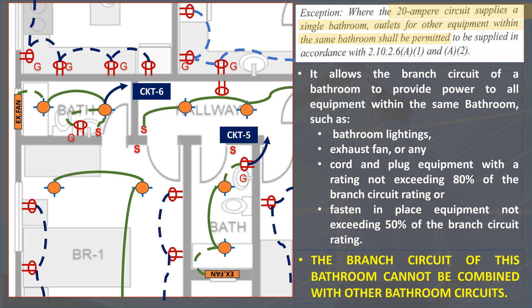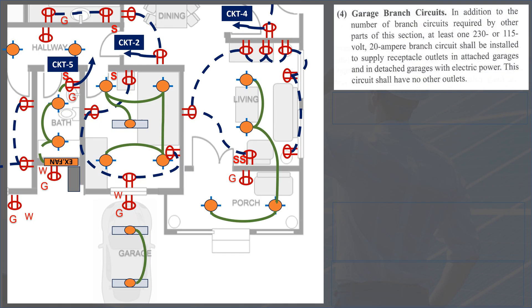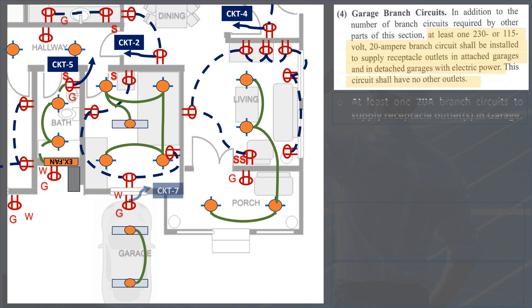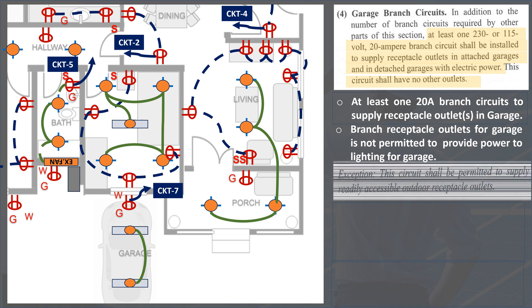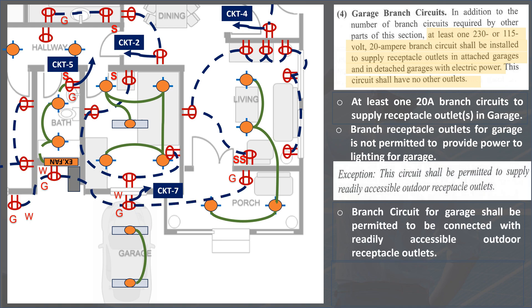The branch circuit of a bathroom cannot be combined with other bathroom circuits. Garage branch circuits: paragraph 4 of Section 2.10.1.11C states that in addition to the number of branch circuits required by other parts of this section, at least one 230V or 115V, 20A branch circuit shall be installed to supply receptacle outlets in attached garages and in detached garages with electric power. This circuit shall have no other outlets. However, per the exception, this branch circuit is permitted to provide power to readily accessible outdoor receptacle outlets. Readily accessible means being reached quickly without the use of a portable ladder.